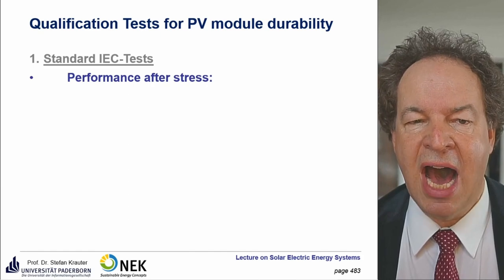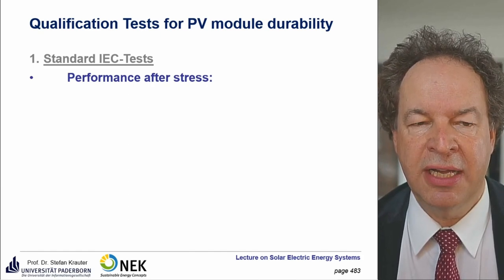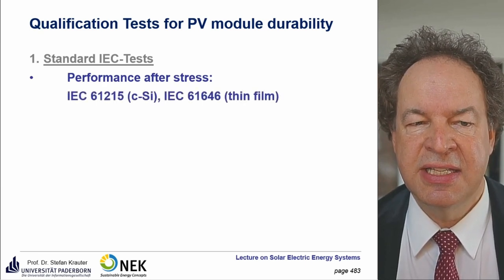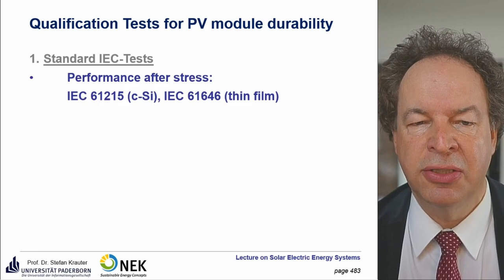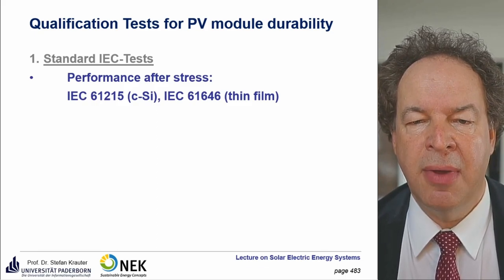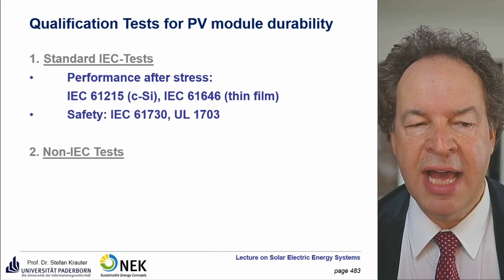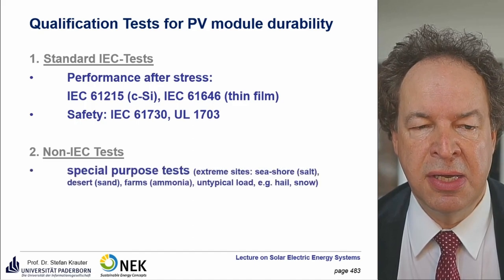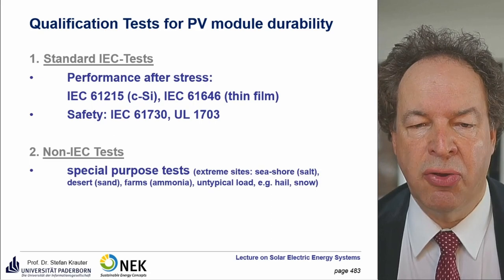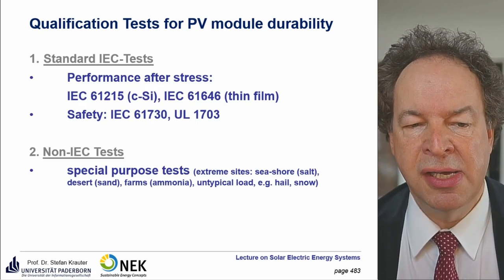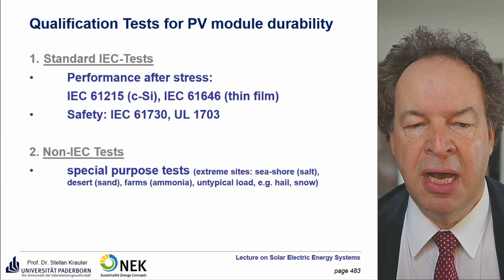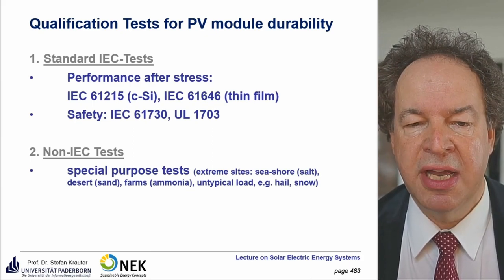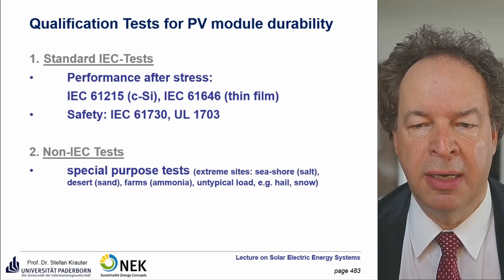These tests assess performance after mechanical, thermal, or electrical stress. The IEC 61215 standard applies to crystalline silicon modules and IEC 61646 to thin-film modules. Additionally, non-IEC tests cover issues not addressed by the IEC tests — special purpose tests for extreme sites, such as salt tests for seashore locations, sand tests for desert locations, ammonia tests for farm environments, and tests for heavy snow or hail loads.